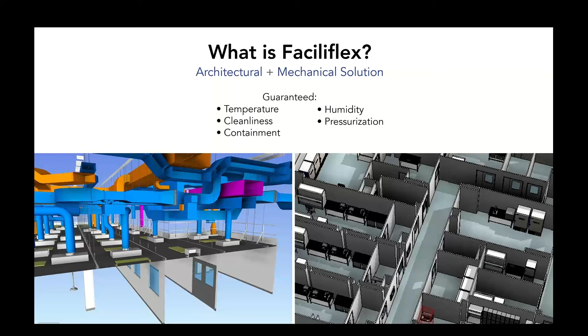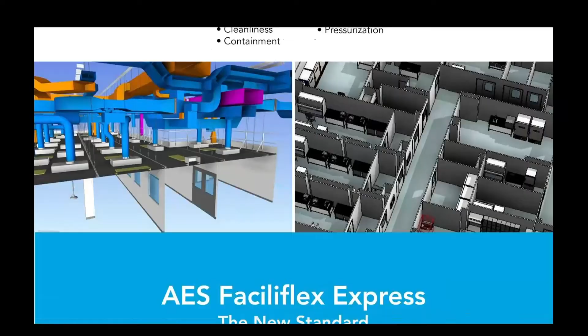So we're looking at how we keep the sensible heat within the room at a comfortable level for people interacting with it. For example, we have a number of biosafety cabinets, perhaps incubators, that will put off some heat, and that could moderate or adjust the amount of CFM we're providing per room. The grade classification of each space also influences how much CFM and the number of HEPA fan modules we include in each space.